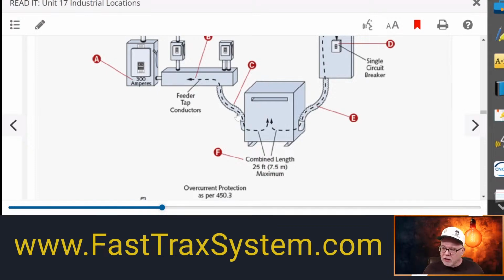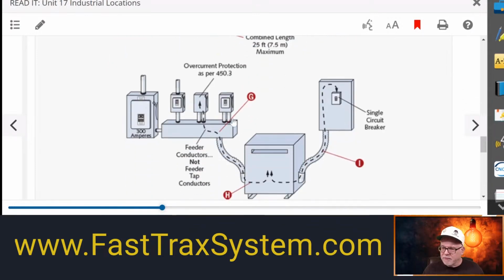Now, one of the quick things I want to point out is this. So this is the other common application right here. This is a scenario where this is not a feeder tap. This is simply supplying a transformer, no different than pulling it from a breaker in a panel. And so this is your overcurrent protection. This would be sized just like what we did earlier, up to 250%, because there is primary and secondary protection.